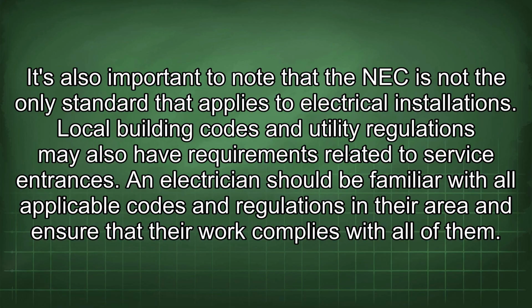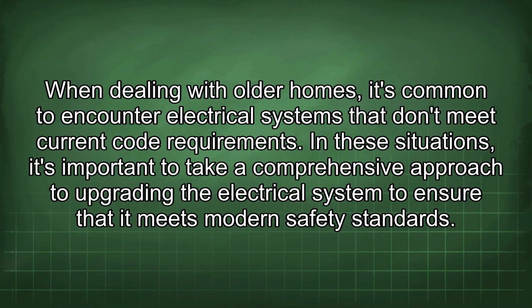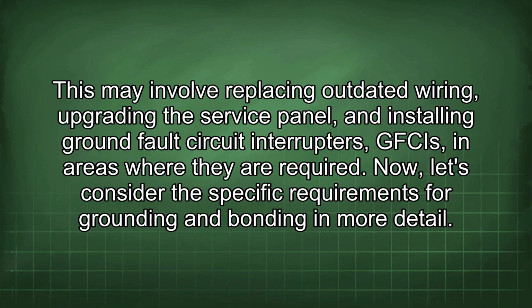Local building codes and utility regulations may also have requirements related to service entrances. An electrician should be familiar with all applicable codes and regulations in their area and ensure that their work complies with all of them. When dealing with older homes, it's common to encounter electrical systems that don't meet current code requirements. In these situations, it's important to take a comprehensive approach to upgrading the electrical system to ensure that it meets modern safety standards. This may involve replacing outdated wiring, upgrading the service panel, and installing ground fault circuit interrupters, GFCIs, in areas where they are required.